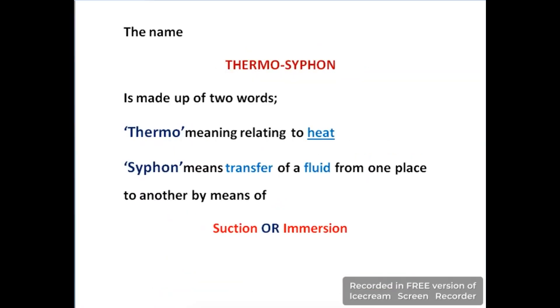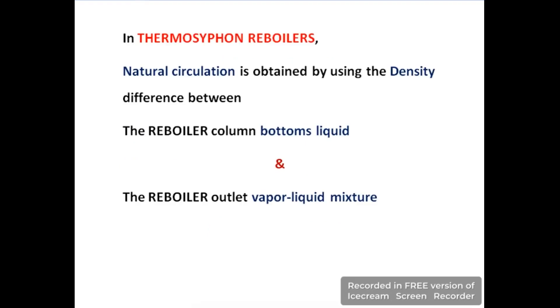The name thermosyphon is made up of two words. The first is 'thermo,' meaning heating. The second is 'siphon,' which means the transfer of a fluid from one place to another through suction or a similar process. In thermosyphon reboilers, the incoming liquid and outgoing vapors flow due to natural circulation. The driving force behind this natural circulation is the density difference between the reboiler column bottom liquid and the outlet vapor-liquid mixture.